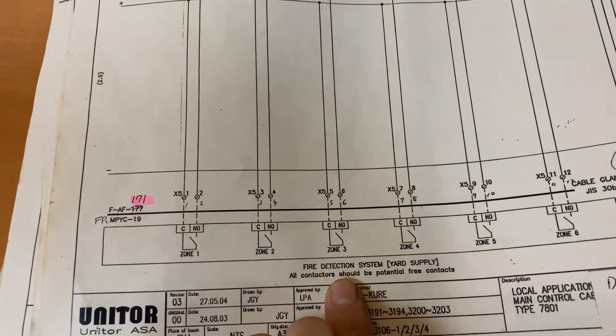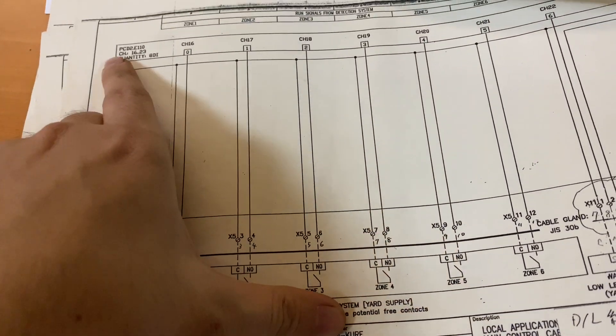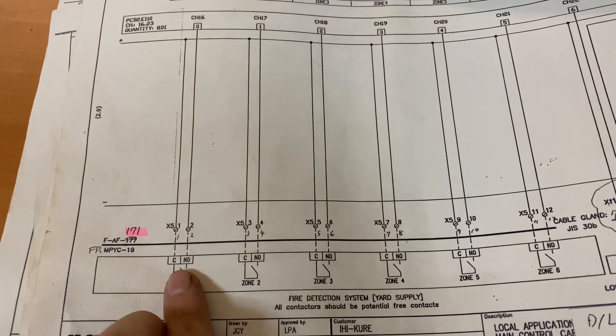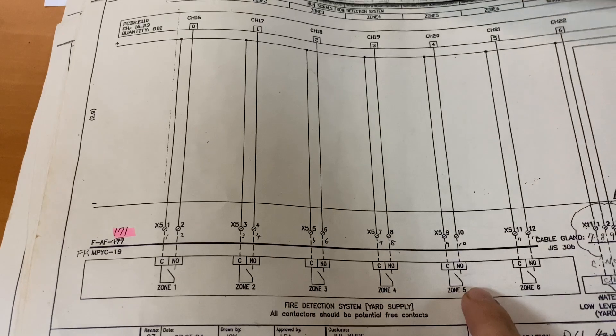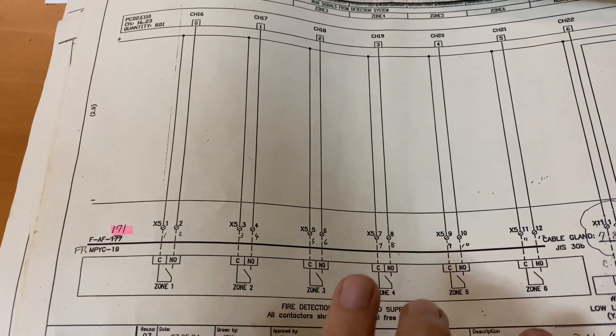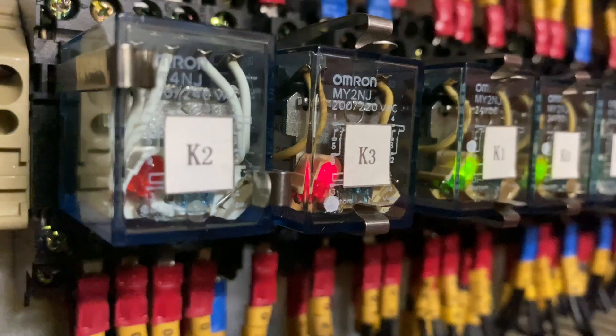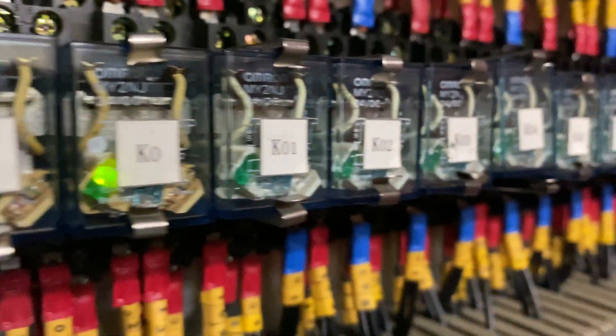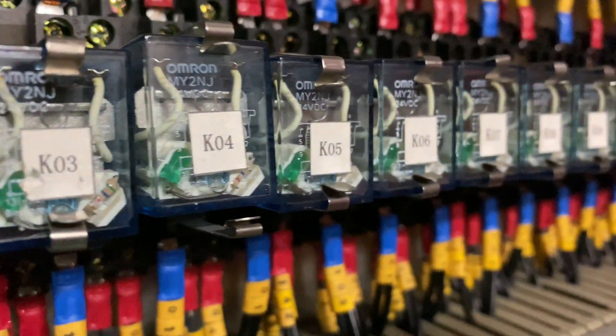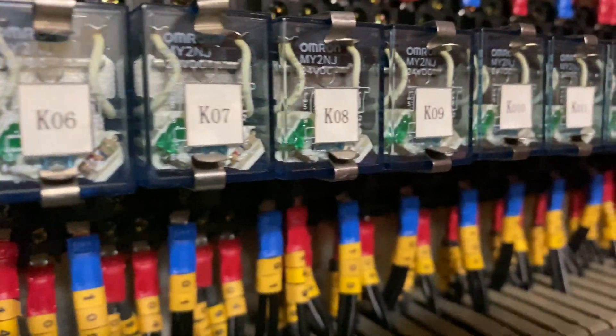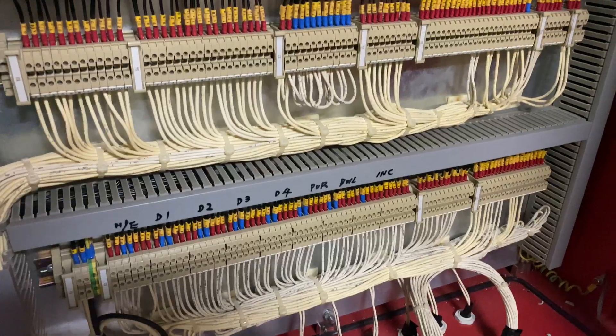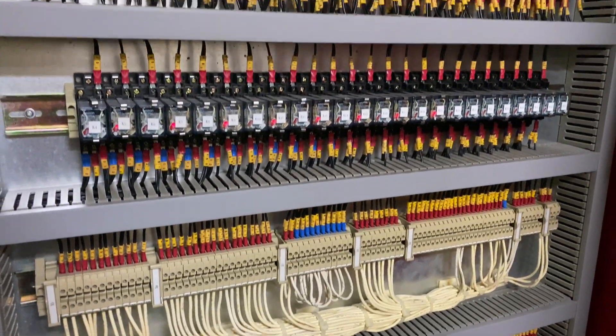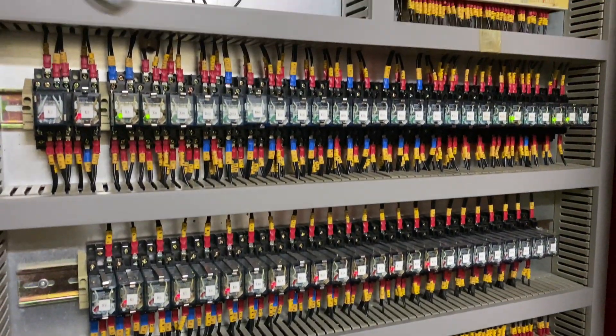I was thinking that the communication between the fire detection system and the PCD2 is not correct. So all I need to do is swap all these wires depending on which is the correct zone.